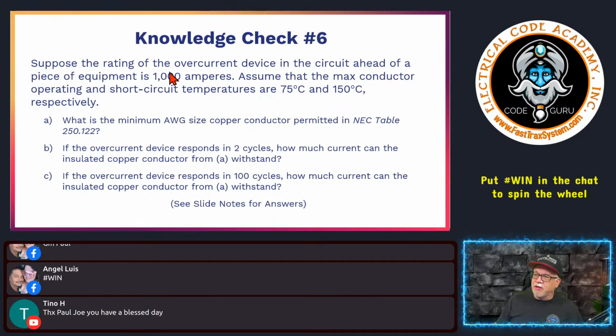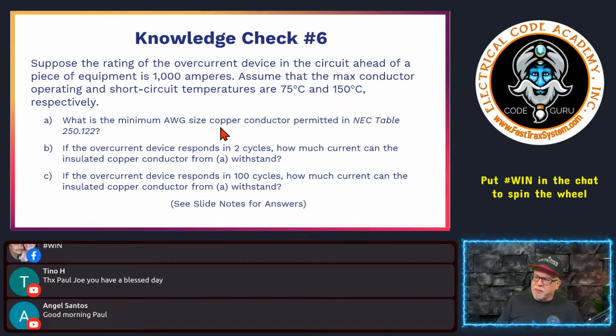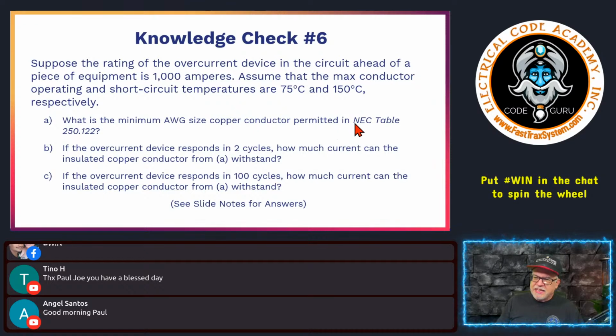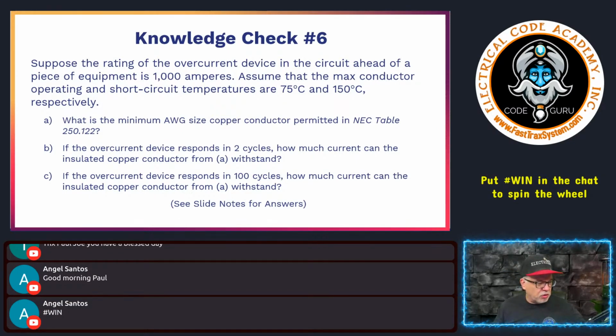All right. Suppose the rating of the overcurrent device in the circuit ahead of the piece of equipment is 1,000 amps. Assume that the maximum conductor operating and short circuit temperature is 75 degrees C and 150 degrees C respectively. It says, what is the minimum AWG size copper conductor permitted in Table 250.122? Okay, so let's go real quickly to the NEC.